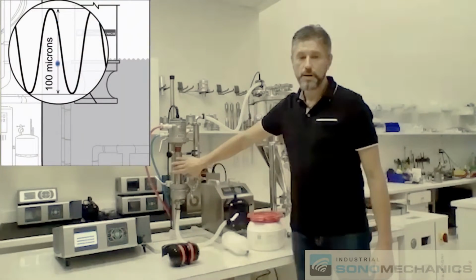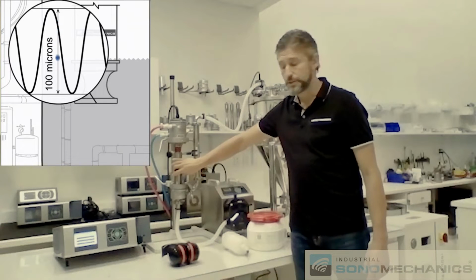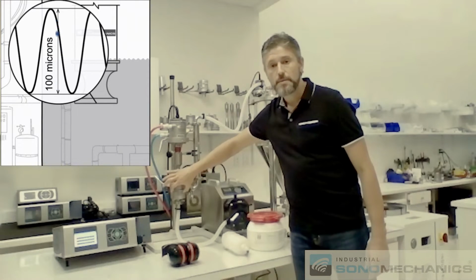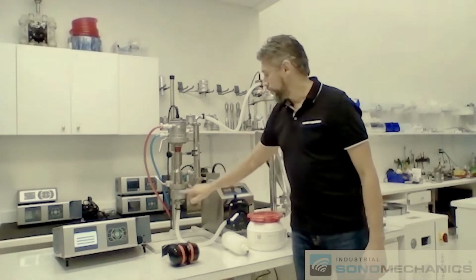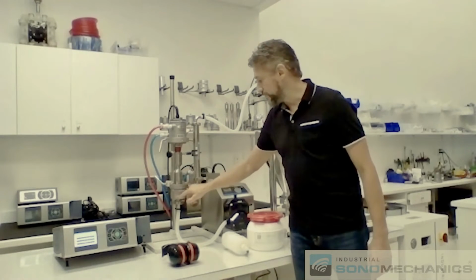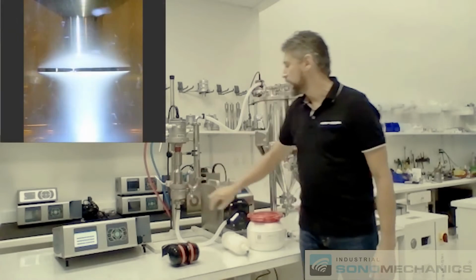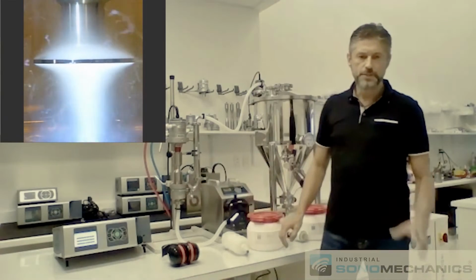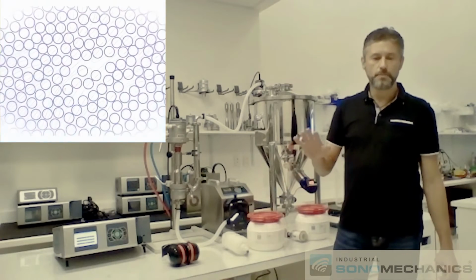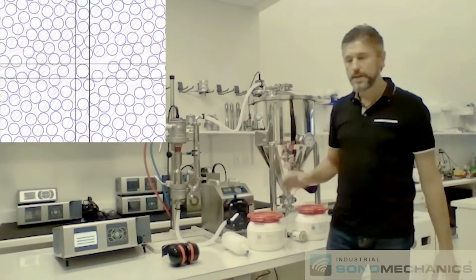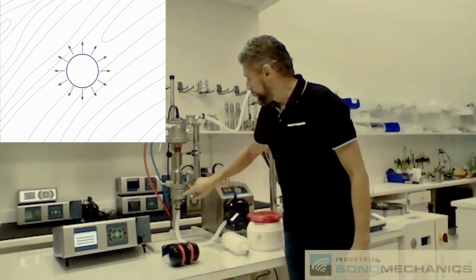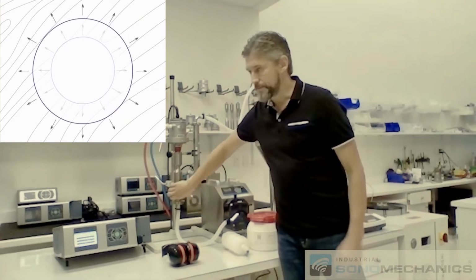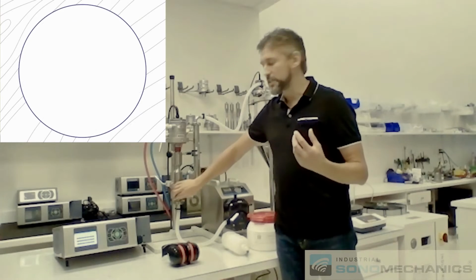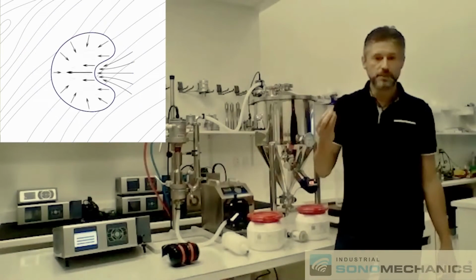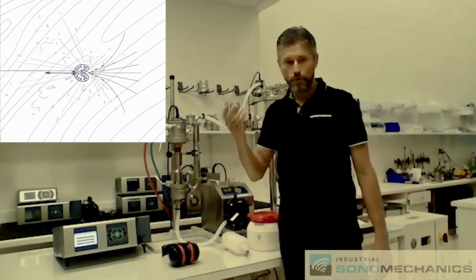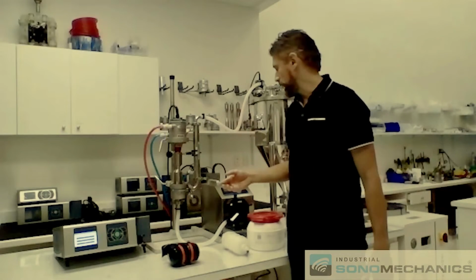This Barbell horn can provide up to 100 microns peak-to-peak ultrasonic amplitude, and it has a 45 millimeter diameter tip, which creates an extremely high acoustic cavitation inside this reactor chamber. Typically, 100 microns is a bit too much, so you normally would operate at about 80% of that value, which is about 80 microns peak-to-peak. This cavitation is the force behind the process. That's what's responsible for the creation of the extremely small droplets of oil suspended in water, which is the nanoemulsion.